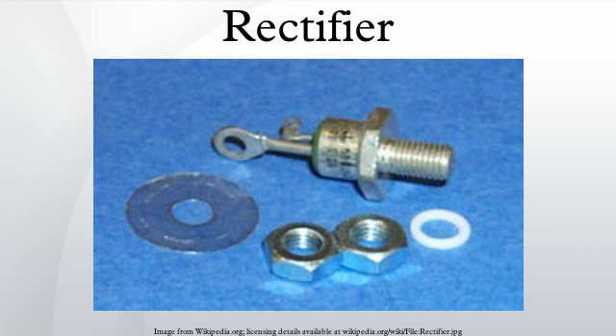Before solid-state devices became available, the half-wave circuit, and the full-wave circuit using a center-tap transformer, were very commonly used in industrial rectifiers using mercury-arc valves. This was because the 3 or 6 AC supply inputs could be fed to a corresponding number of anode electrodes on a single tank, sharing a common cathode. With the advent of diodes and thyristors, these circuits have become less popular and the three-phase bridge circuit has become the most common circuit. Three-phase bridge rectifier.